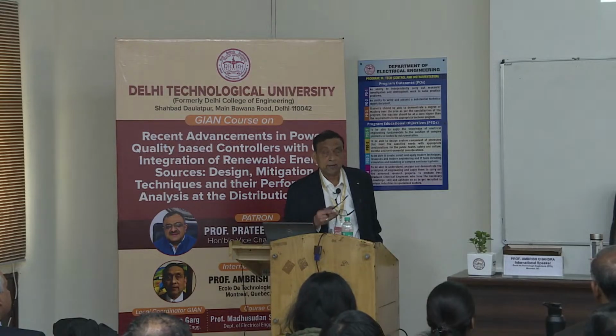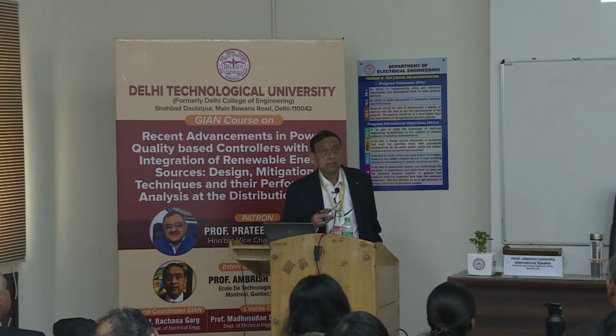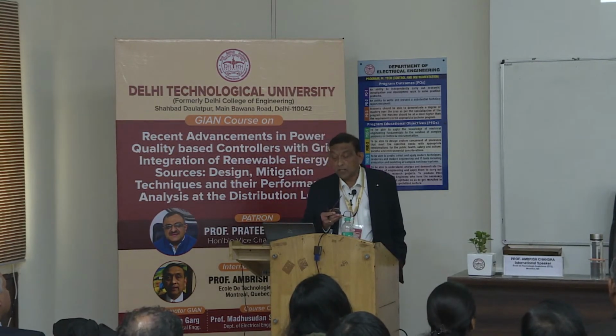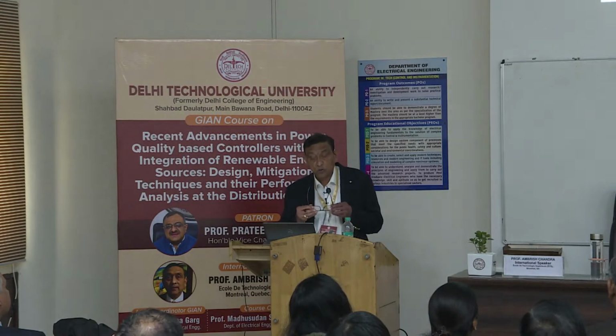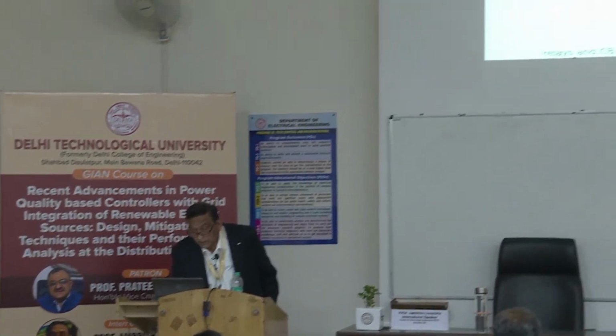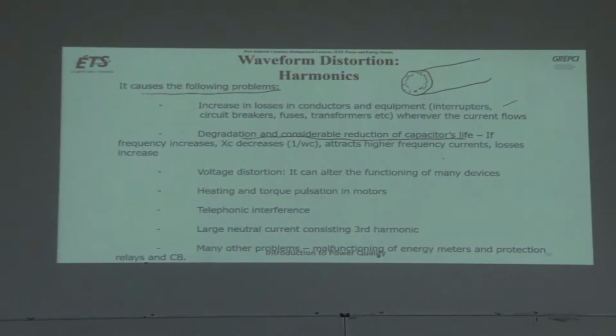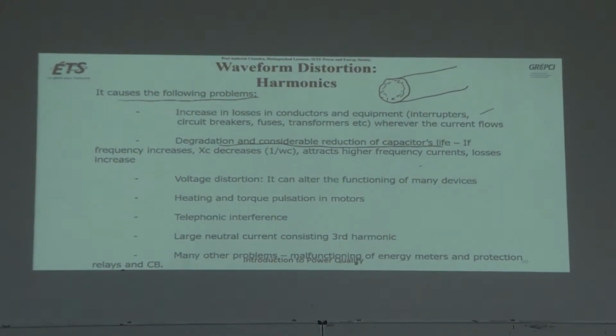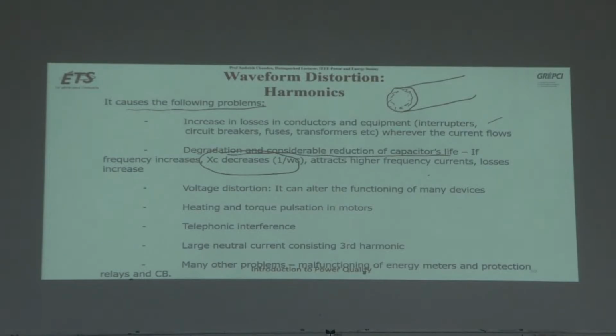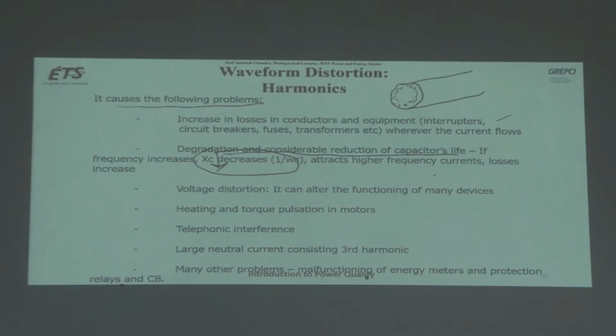You will have to derate the transformer, otherwise it will decrease the life of the transformer because of the extra losses. Degradation and considerable reduction of the capacitor's life, because of the capacitive reactance, 1 upon omega C. So if frequency increases, then Xc will decrease and it will attract the higher frequency currents. So more higher frequency current will be attracted by your capacitor.